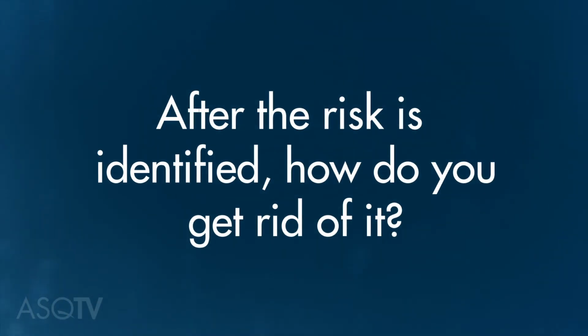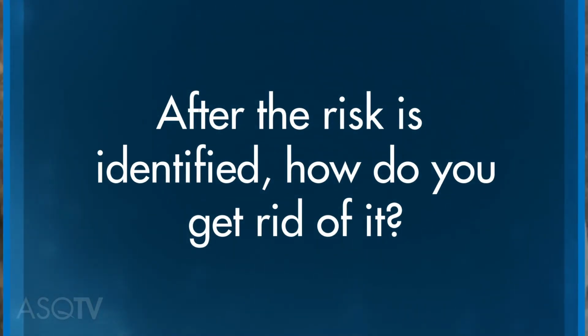You must first begin by defining what we call an objectionable incident. So in the case of a customer requirement, an objectionable incident would be you get the wrong requirement. In the case of a design, that would be a design failure. In the case of manufacturing, that would be producing a product out of spec. Once I identify what the objectionable incident is, the next step is to define the harm and the severity of harm. So we basically have to ask, when this objectionable incident happens, what's the potential impact?